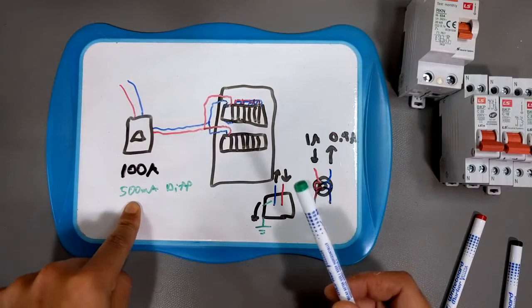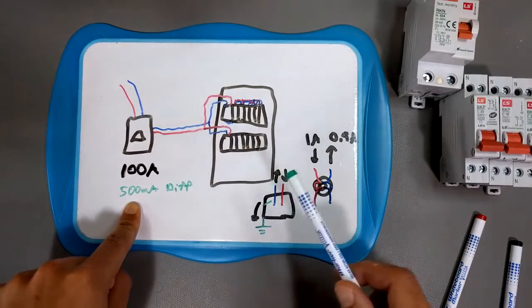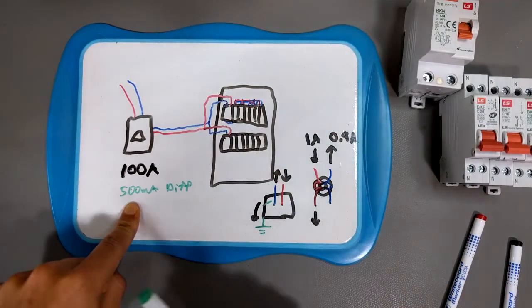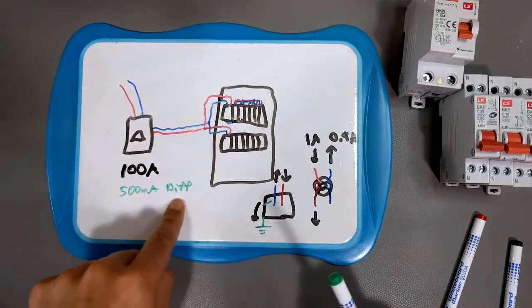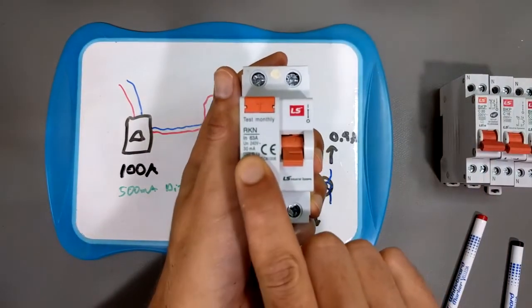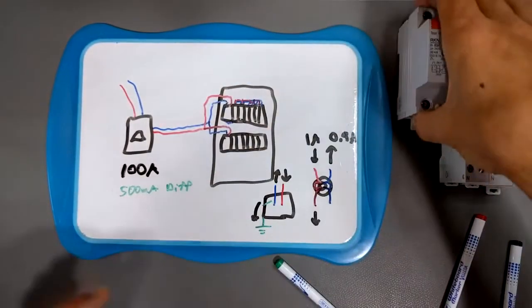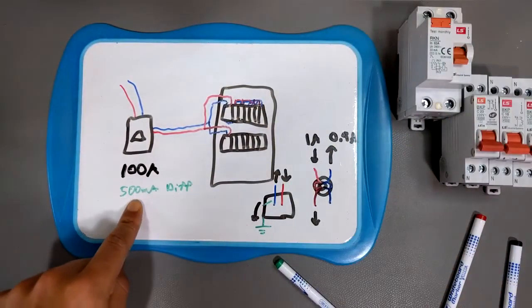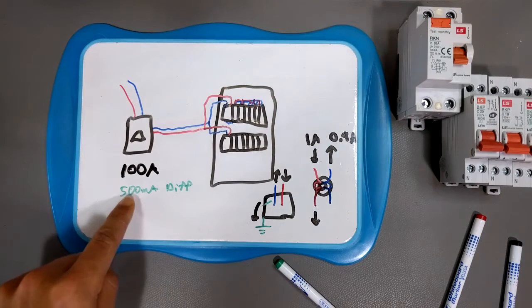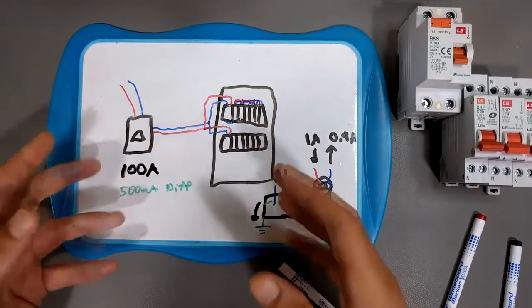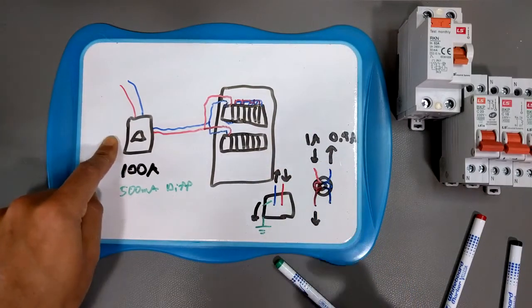But he also has this, usually, sometimes it's 300, where I live it's 500 milliamps, 500 mil differential detection, which is obviously much higher than 30 mil. And the reason for that is usually fire prevention. So if there's 500 mils or more of leakage current, this guy's going to trip.